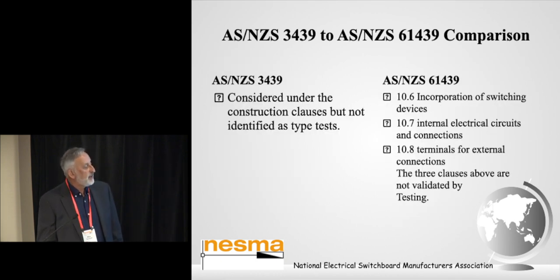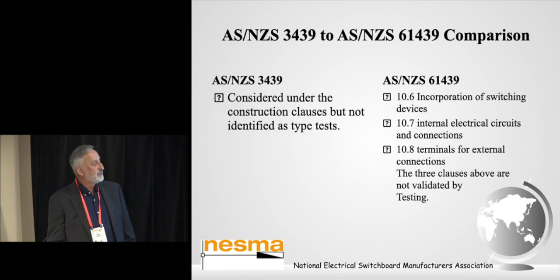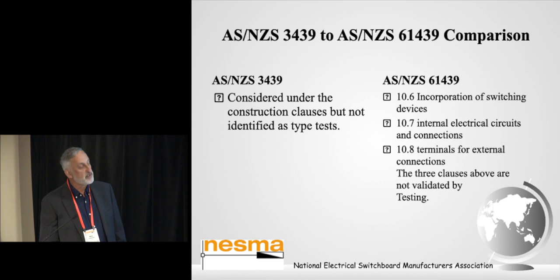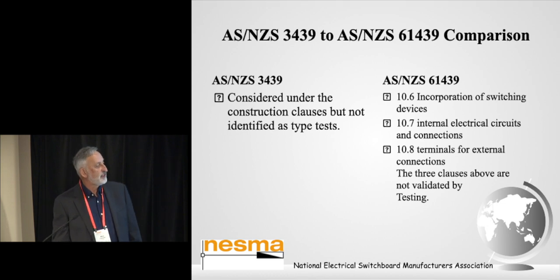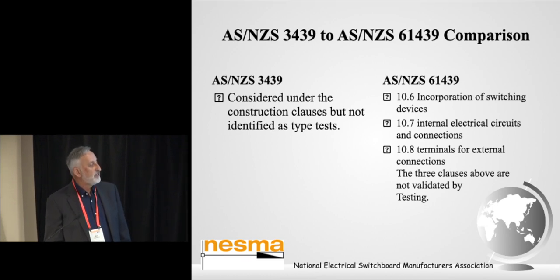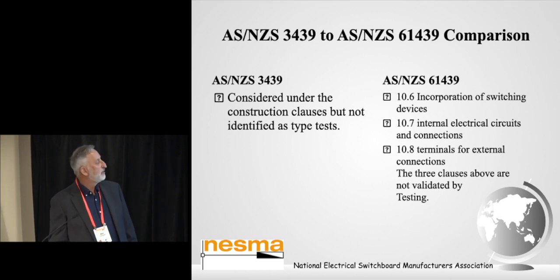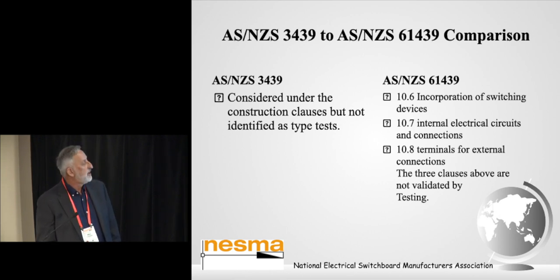The 61439 also brings some additional clauses in 10.6, 10.7, 10.8, which is the incorporation of switching devices, internal electrical circuits and connections, and terminals for external connections. The three clauses above are not validated by testing, but they were handled roughly under the 3439 by being considered under the construction clauses, but not identified as type tests.